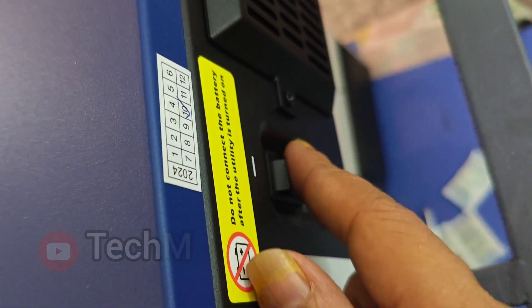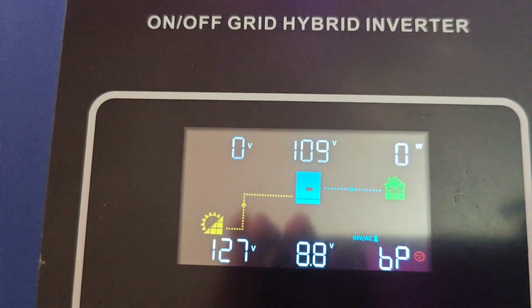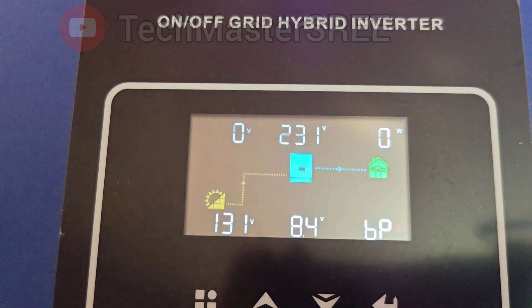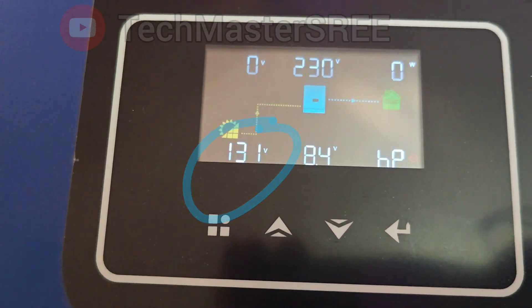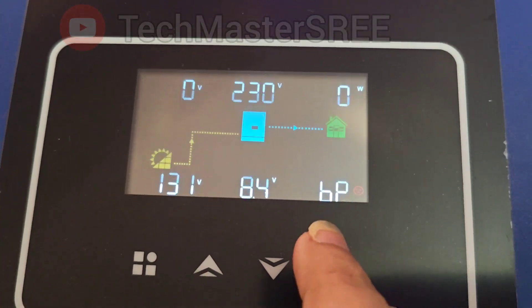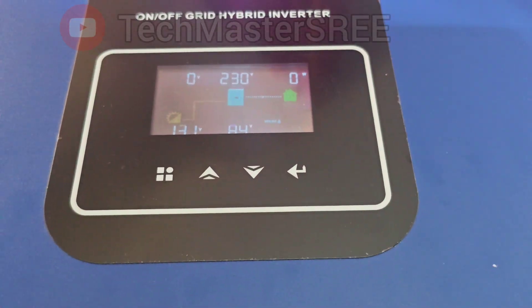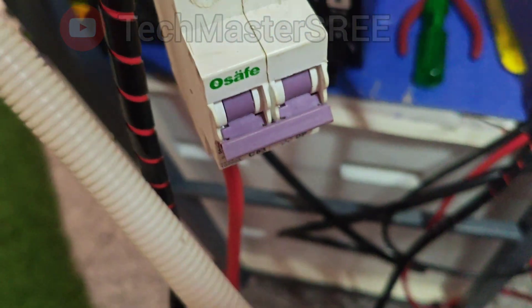I am going to turn on the solar breaker only. After turning on the inverter, we can see lines from solar to inverter and from inverter to home load, indicating the inverter is on. From the screen we can identify: solar panel voltage is 131 volts, output is 231 or 230 volts, and it's showing 'BP' because the battery is not present. The connected load is shown at the top. Right now I have connected only one bulb.